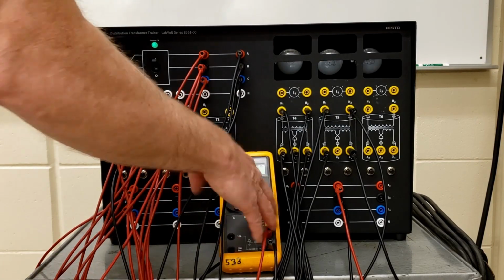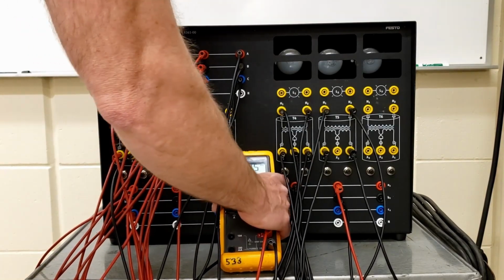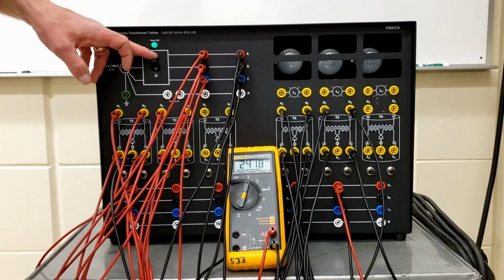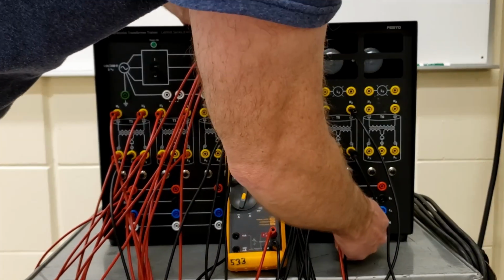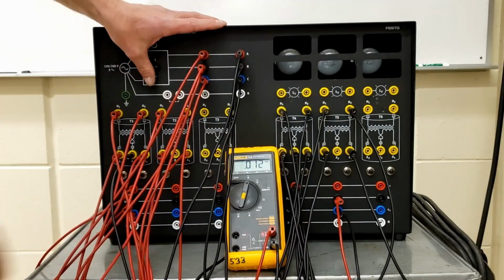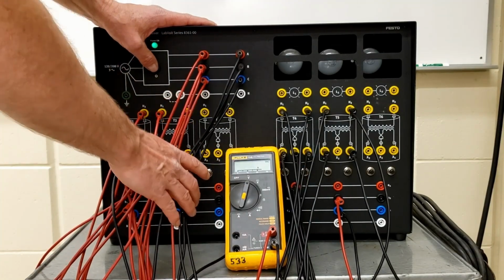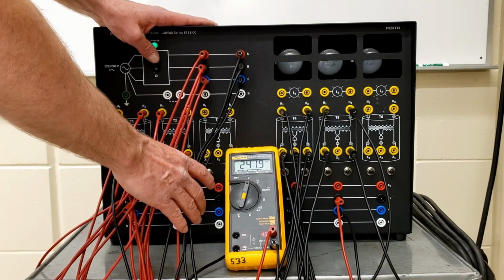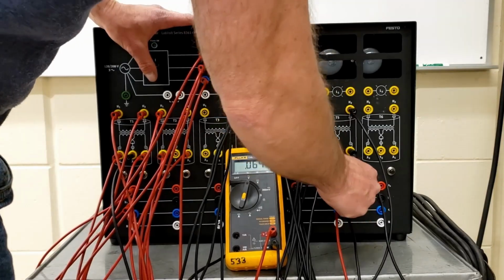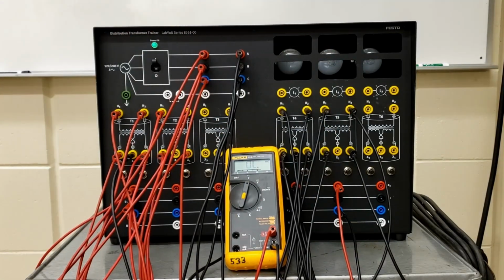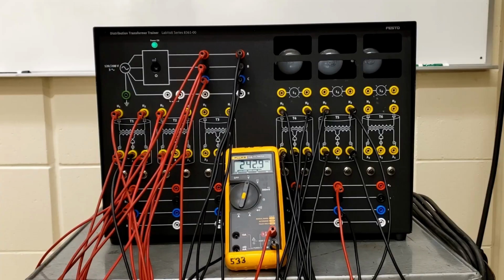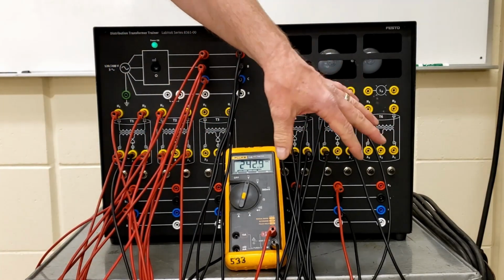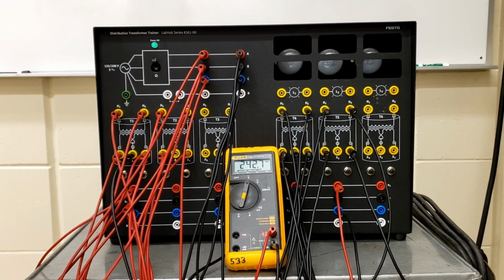Okay, let's take a look at the B and the C. Okay, so B and C should also be 240. Looks good, 242. And between C and A, we should see 240 volts as well. Very nice. Okay, so even though we have them 180 degrees out of phase compared to the first transformer, the secondary voltages are still at 240.